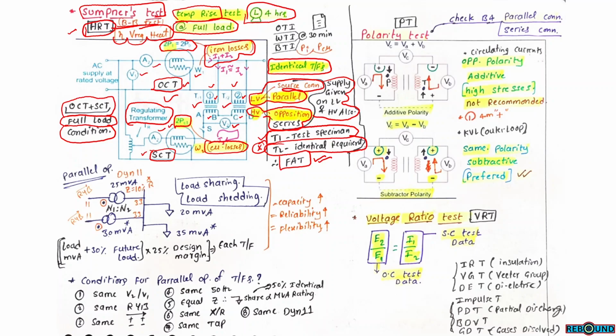During testing, we have to record OTI, WTI, and body temperature regularly at every 30 minutes, and iron losses and copper losses are to be calculated and the same must be recorded. So the open circuit test, short circuit test and Sumpner's test are important tests, and other tests are the polarity test, voltage ratio test and others. The polarity test is very important to connect the transformers in parallel. So this has to be verified before connecting the transformers in parallel or in series condition.